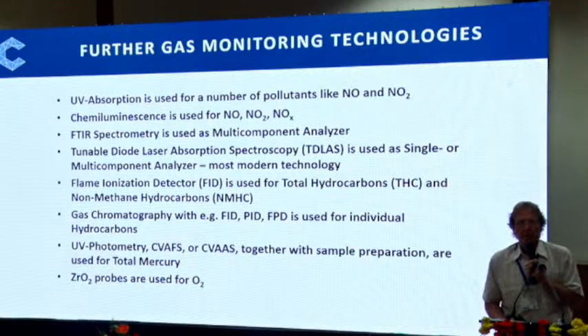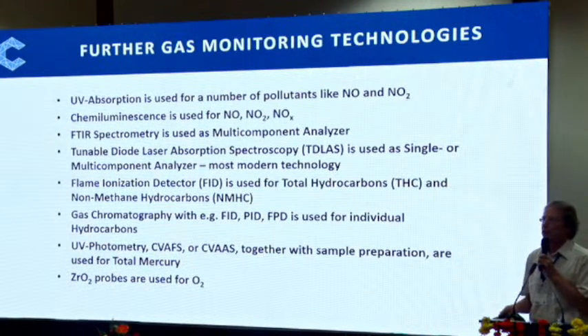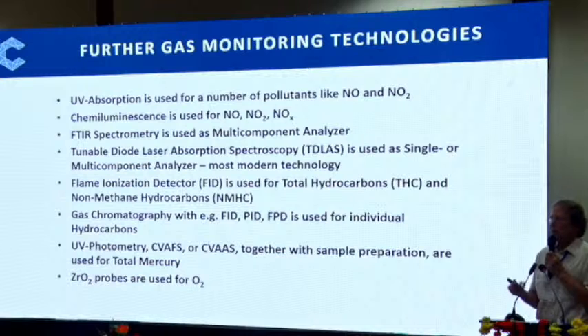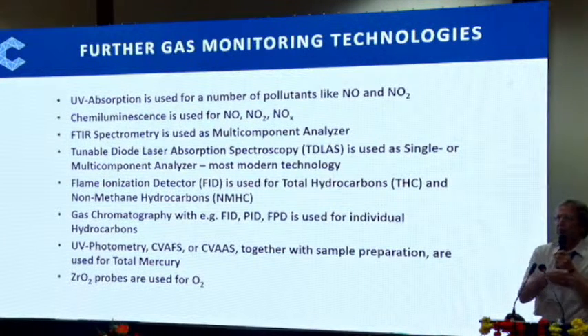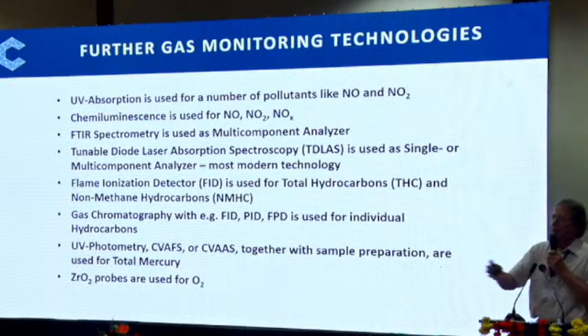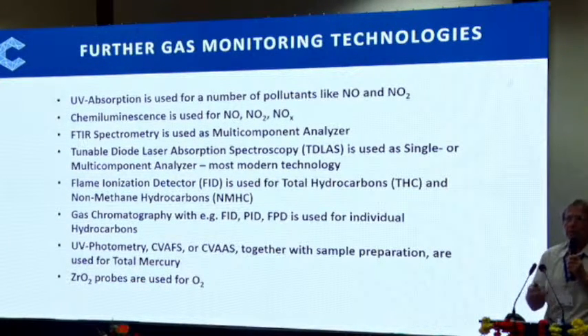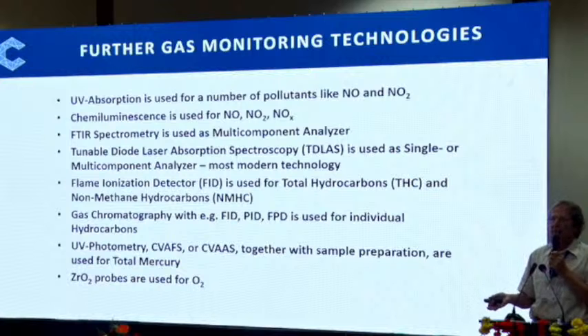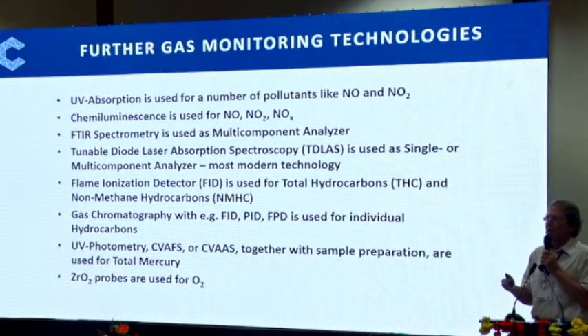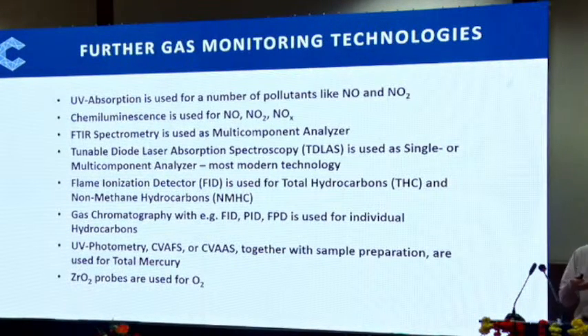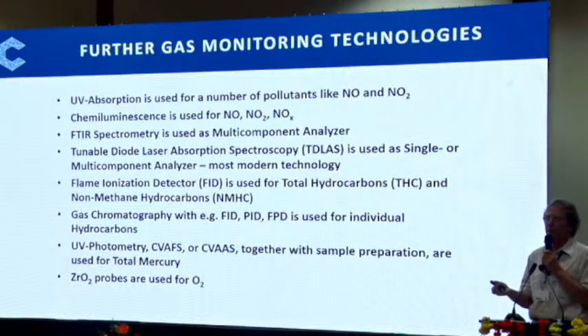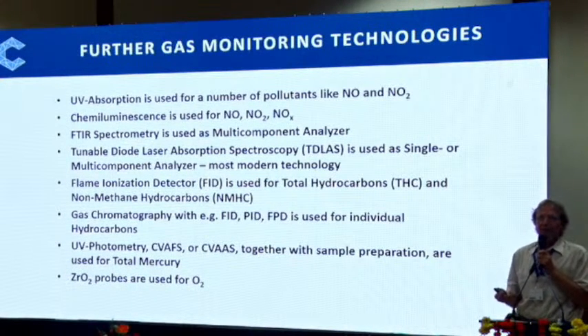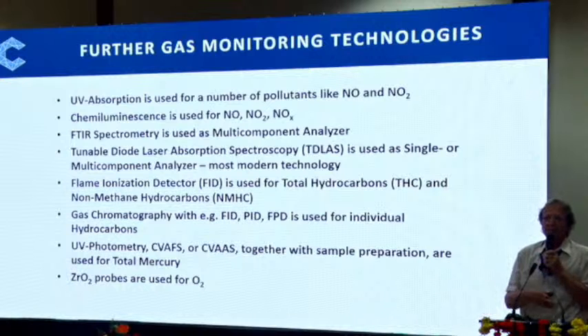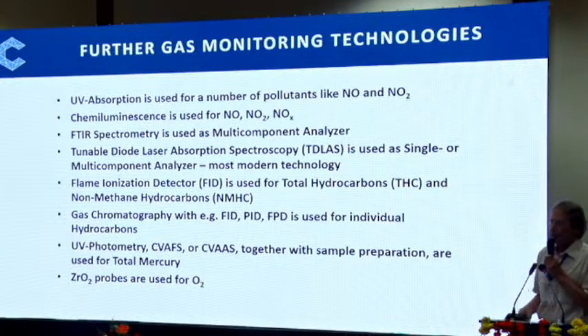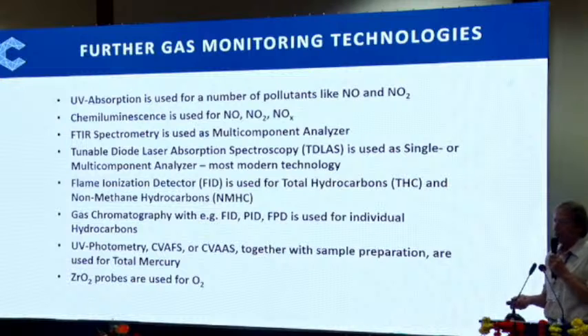Then FIDs, flame ionization detectors, for detection of total hydrocarbons, because total hydrocarbons is a summary of hundreds, thousands, or whatever, of carbon-based components, so organic, not inorganic carbon-based. Inorganic carbon-based is CO and CO2. Organic carbon-based is everything else. And the FID measures that in a summary signal.